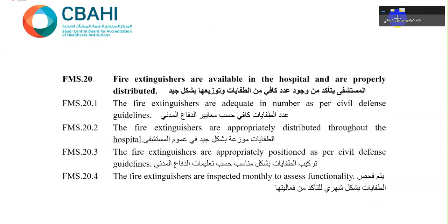Number 20, we have to make sure that the number of extinguishers is as per civil defense guidelines, and appropriately distributed and installed as per civil defense. Then we have to check the fire extinguishers on a monthly basis. The height of the extinguishers: actually, NFPA and Saudi Building Code have identified the height, as you see here. For instance, if you have a fire extinguisher less than 18 kilograms, the height will be 1.5 maximum. Of course, the lever height. If it's more than 18 kilograms, then the height would be 1.1 meter, with one condition, should be 10 centimeters above floor level.